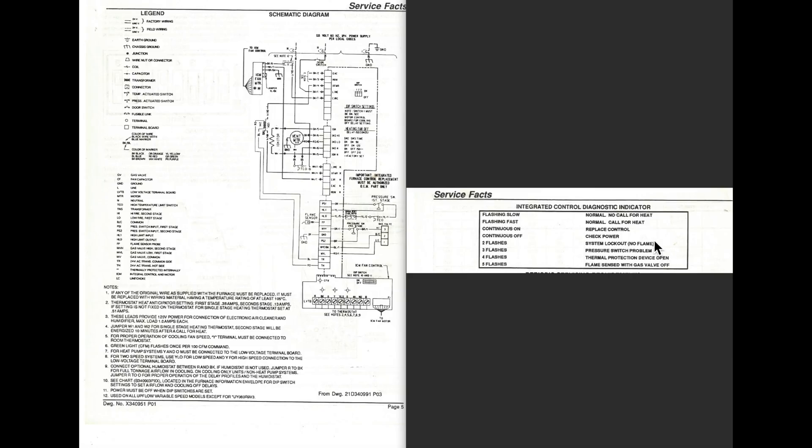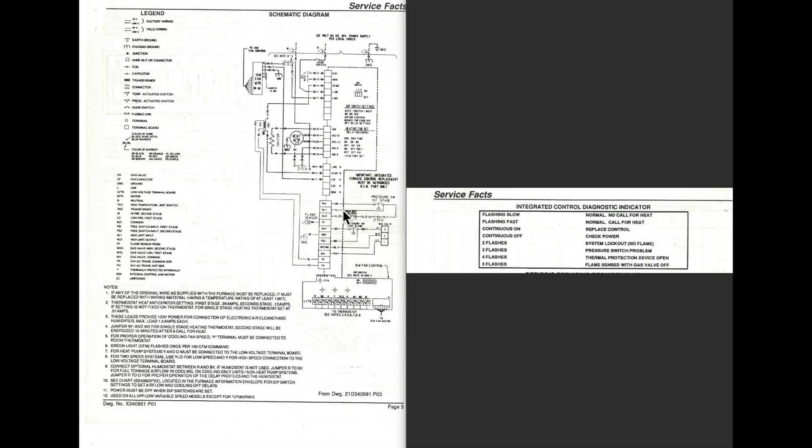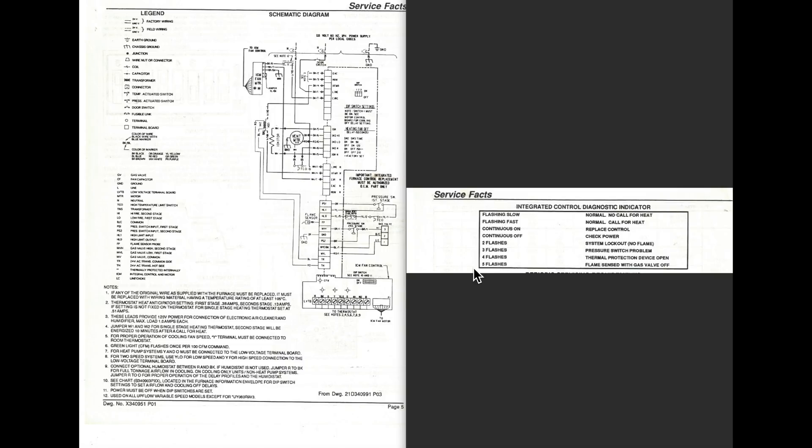System lockout, of course, no flame. That means hot surface igniter didn't come on, flame sense didn't sense flame, gas valve didn't come on, no gases available, something like that. And of course, your thermal protection, that's right here. These are not going to let this furnace start. In fact, they're going to leave the fan motor on. The fan motor will start if you have the thermal protection open. And I don't know what's going to happen with the flame sense with the gas valve off.